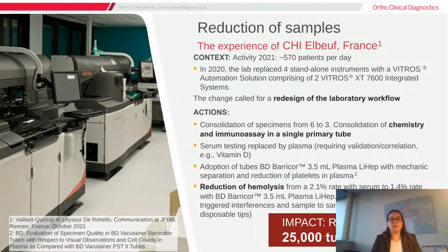Here, I want to bring you a real case study and customer experience. First of all, let me give some context. In 2020, a lab in France replaced 4 standalone instruments with a Vitros automation solution comprising 2 Vitros XT 7600 integrated systems.